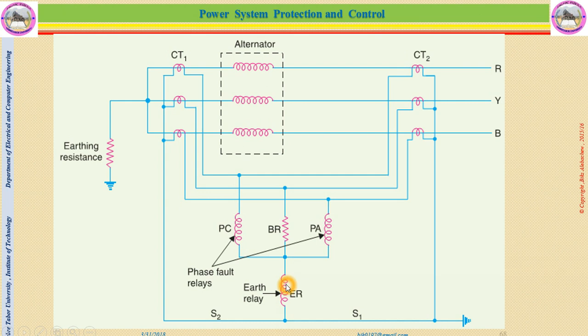This is more sensitive than when you compare the PC and PA relays. When you say more sensitive, the pickup current is less than the other. So in that time, if the earth fault happens, the current will pass through this earth relay. In that condition, this earth relay will trip even if the fault is small.